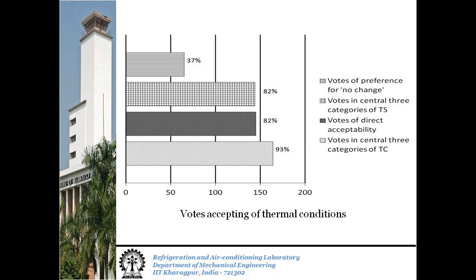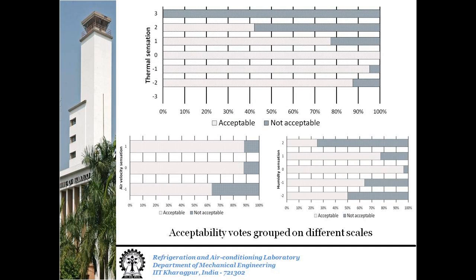While three of the criteria give relatively similar values, thermal preference is too stringent a criterion for judging acceptability. As a gross evaluation, we can see that satisfaction over the whole survey remains over 80%. Examining responses to the acceptability question, we see that votes on the cooler side of the thermal sensation scale are more accepting, as are votes that feel air movement is just right or even breezy.